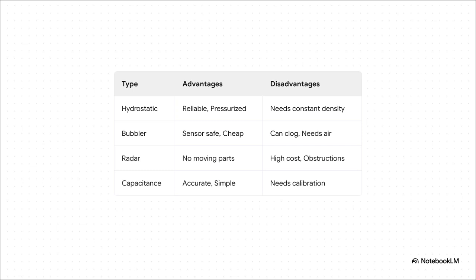The hydrostatic sensor is super reliable, but its accuracy can get thrown off if the liquid's density changes, say with temperature. The bubbler is cheap and keeps the sensor clean, but that tube can get clogged. Radar is great, no moving parts, but it costs more and can get confused by pipes or other things inside the tank. And capacitance? It's really accurate, but you have to calibrate it carefully for every single type of fluid. It is always a balancing act to pick the right tool for the job.